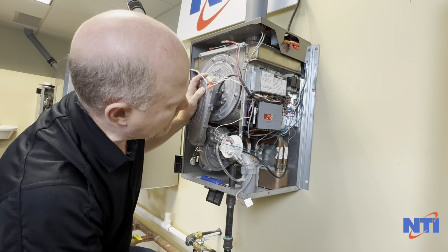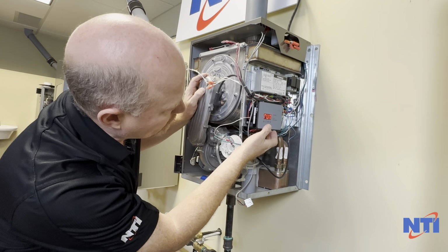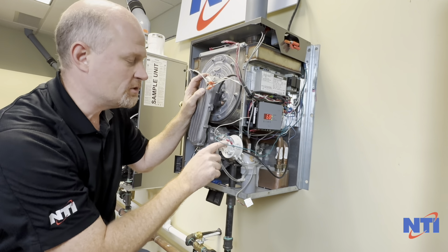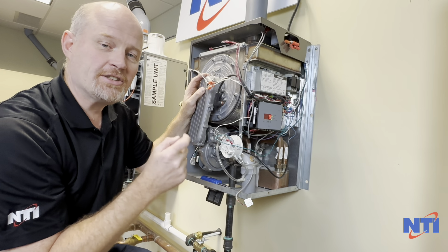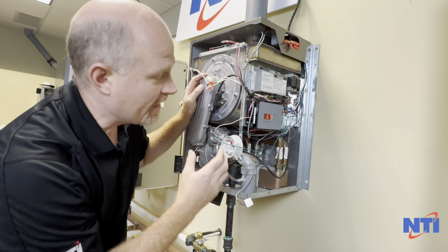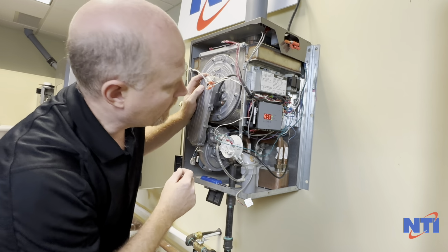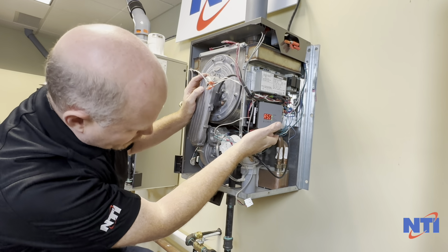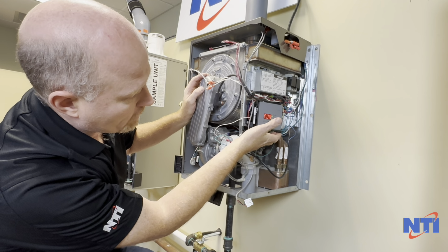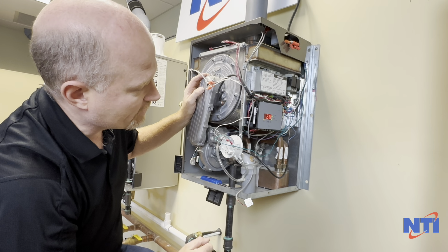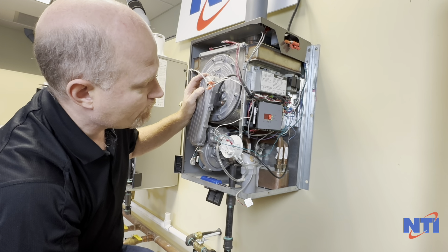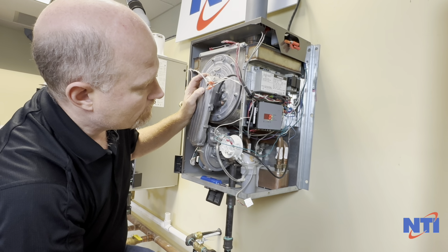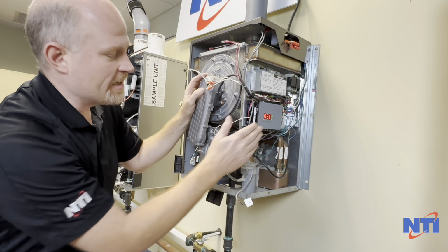Now that we've connected that, let's see what our boiler does. So it's now attempted to ignite. What I'm going to do is just reset the boiler to see what it does from a start. What will happen is when you jumper this contact, if you catch it at just the right time, you might actually fool the boiler into trying to fire. So we've actually gone back to an ASC. If you're not sure, just reset it again. Just double click the function button and just see what it does.